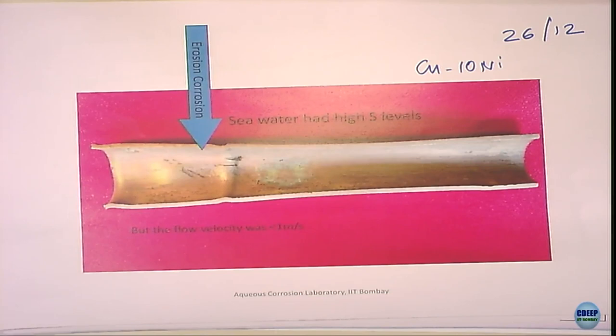Then I asked over phone, okay, what can be the reason? I said maybe microbial corrosion. We have not discussed microbial corrosion so far. For sea water, we thought it could be microbial corrosion because when the velocity is less there can be fouling, and with fouling you get microbial corrosion. So it could happen. This went on, second time problem, third time, fourth time, they got fed up and said let us see what happened.